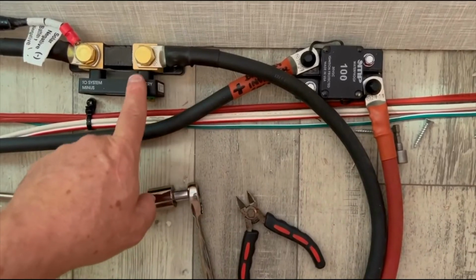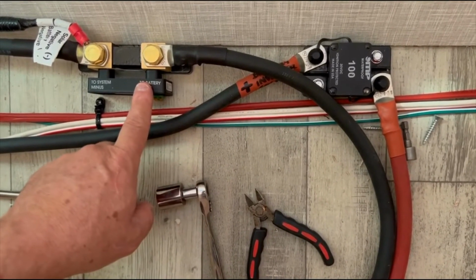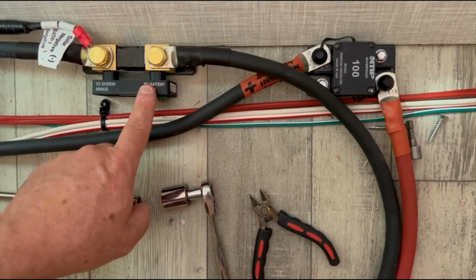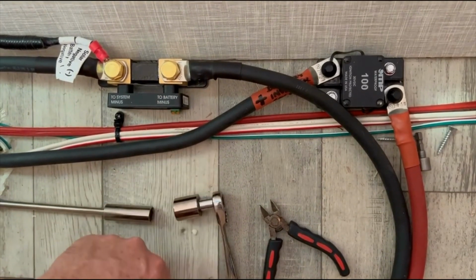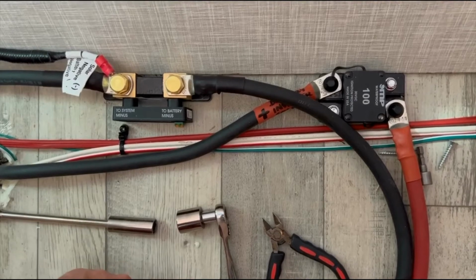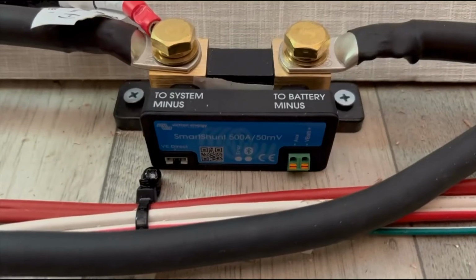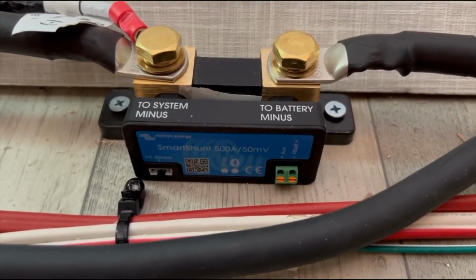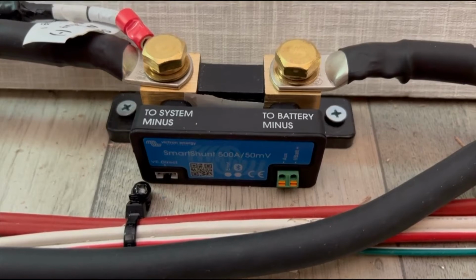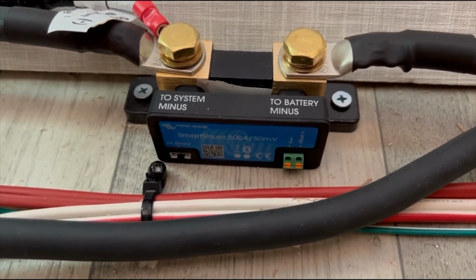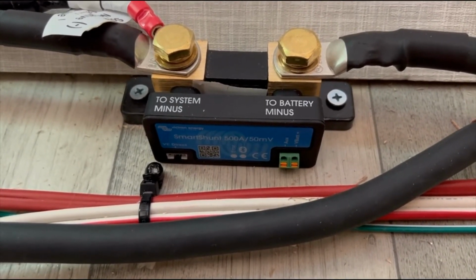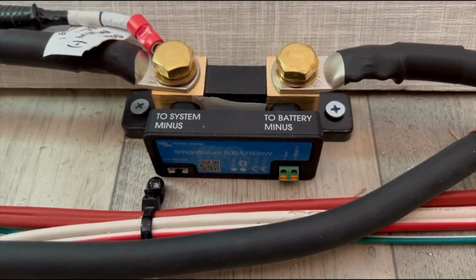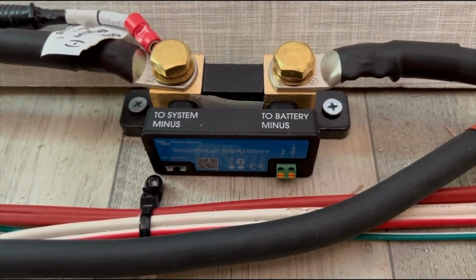But on the back side, we've got negative energy coming back out, and this is a Victron Smart Shunt. This will enable me to accurately monitor the charge status of the battery, the draw, and a whole bunch of other really super cool stuff. If you don't have a shunt in your system and you're relying solely on the Go Power controller on the wall, you're probably not getting a very accurate picture of what your battery is producing and or holding. So if you can replace anything, I would do this.